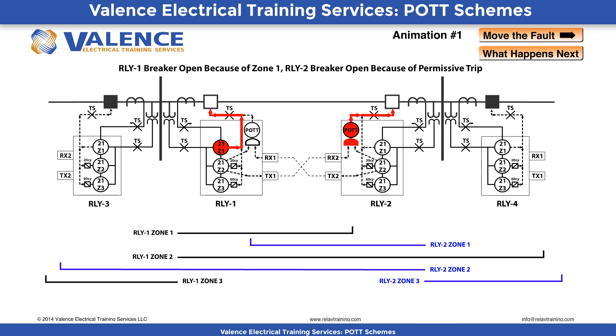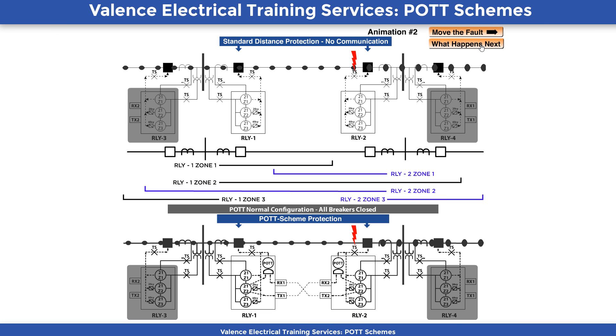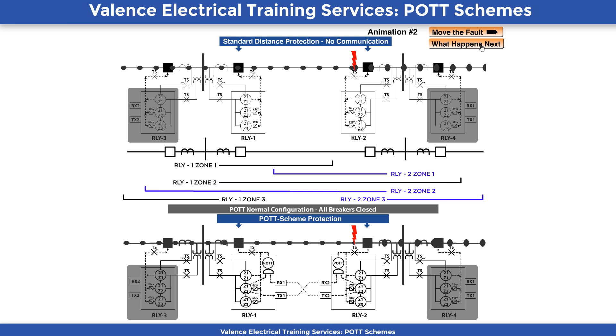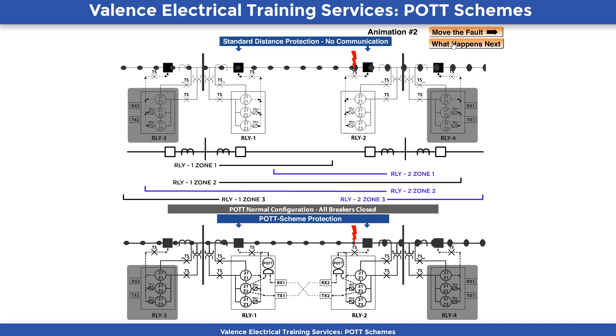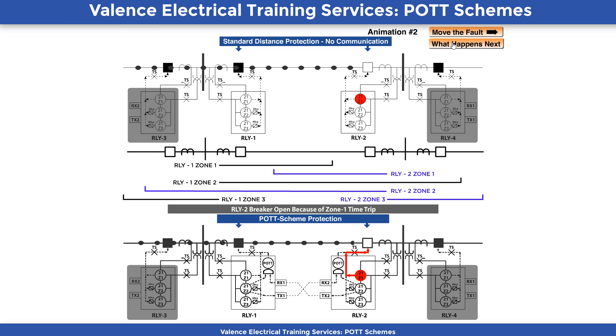Let's look at a fault that is closer to Relay 2, but this time we'll compare it to a standard distance protection scheme. This fault is a mirror image of the previous one, with the standard distance scheme on top of the screen and the POTT scheme shown on the bottom of the screen. This time Relay 2 sees a Zone 1 and Zone 2 pickup, while Relay 1 sees a Zone 2 pickup. Relay 2 will trip instantaneously in both protection schemes because Zone 1 will always trip first as it has no intentional time delay.